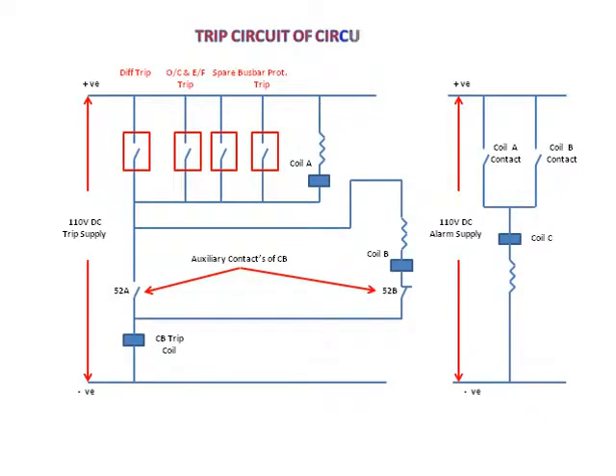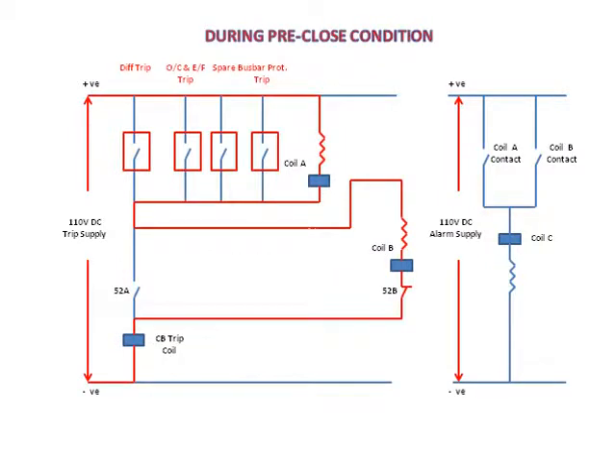The connection of the TCS relay and trip circuit of the circuit breaker will be as shown in the figure. During pre-close condition, the flow of current will be as shown — both coil A and B will be in pickup condition. Since both coil A and B are in pickup condition, coil C will also be picked up as coil A and B contacts close.